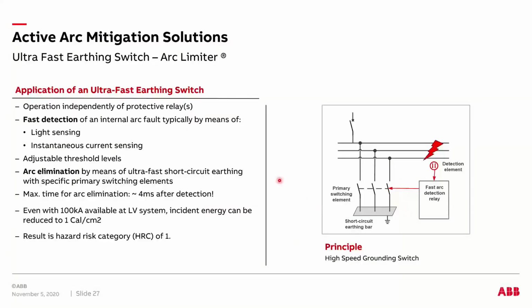I mentioned a couple of active arc mitigation technologies, right? One of them is a fault current limiter, and the other one is the ultra fast earthing switch. For this particular presentation, I'm going to talk specifically about the UFS, but the presentation slides that you guys received should talk briefly about fault current limiters as well, right? So here I'm going to talk about a unique principle where we are going to eliminate an arcing fault in less than 4.5 milliseconds, right?